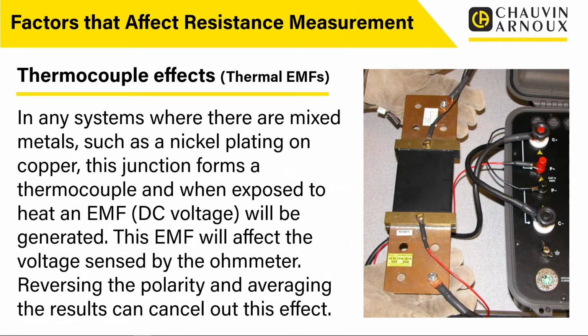So you've probably come across the term thermocouple many times with temperature measurement, but actually thermocouple effects can cause problems when we're doing low resistance measurement. So in any system where there's mixed metals, such as nickel plating on copper, for example, so even on your test leads, if you've got a nickel plating on the outside of your copper probe, for example, or crocodile clips, this junction forms a thermocouple, and when exposed to heat, an EMF, which is basically a DC voltage, will be generated. This EMF will affect the voltage sensed by the ohm meter.